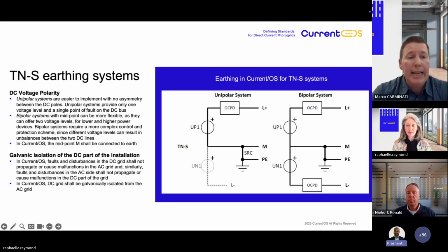But on the other side, we need a more complex system in terms of control and protection scheme. First of all, because, for example, we have to introduce a 4-leg converter, which is able to balance the current inside the midpoint in case of unbalanced load, in order not to have an imbalance in voltages between plus and midpoint and negative and midpoint. And also, if we have a three-wire distribution, so a bipolar system, usually we need at least a 2-pole circuit breaker installed on both plus and minus to detect the earth fault current. In Current OS, if we have a unipolar or bipolar distribution with midpoint, we strictly recommend having the midpoint earthed.